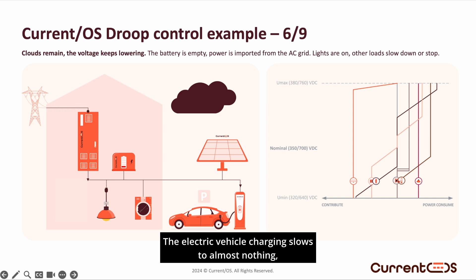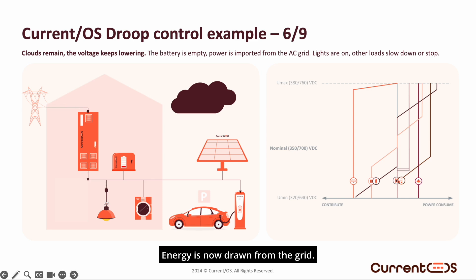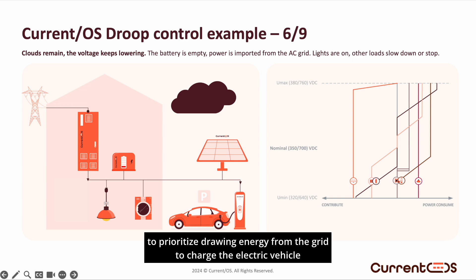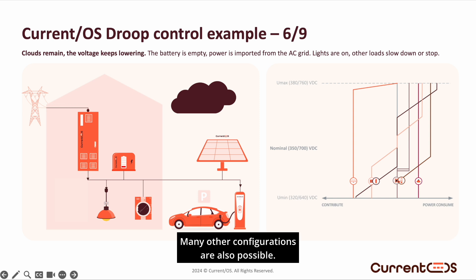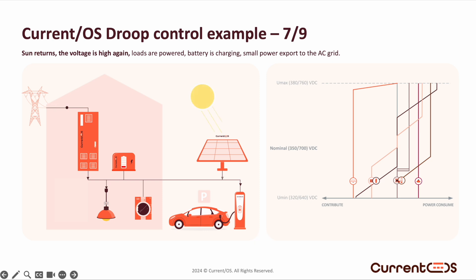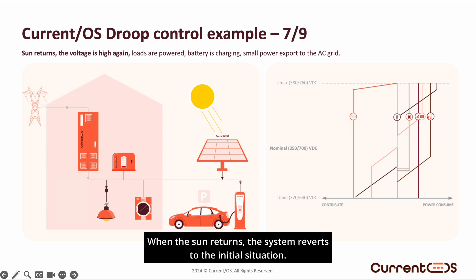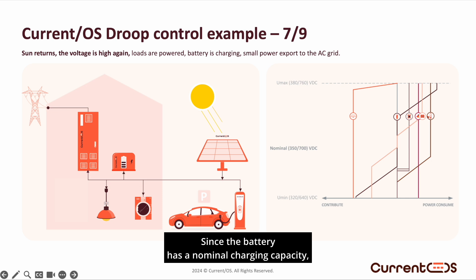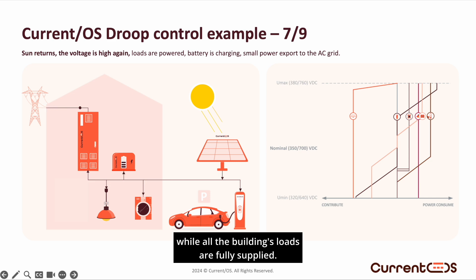The electric vehicle charging slows to almost nothing, while the lighting continues to operate at nominal power. Energy is now drawn from the grid. As a reminder, this is just an example. Through software, the system could be programmed differently — for instance, to prioritize drawing energy from the grid to charge the electric vehicle if it's needed for immediate use. Many other configurations are also possible. When the sun returns, the system reverts to the initial situation: the photovoltaic panels resume full contribution, providing enough power to recharge the battery. Since the battery has a nominal charging capacity, any surplus energy is exported to the public grid while all the building's loads are fully supplied.